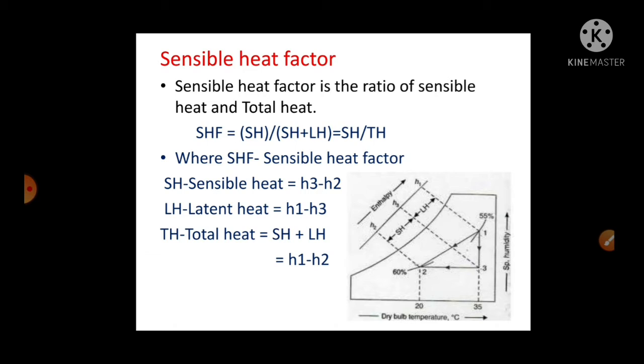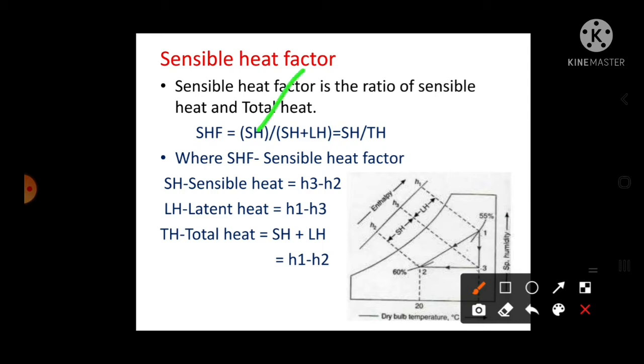Sensible heat factor is the ratio of sensible heat and total heat. So SHF is sensible heat divided by the total heat. So what is total heat? Total heat is nothing but the sensible heat and latent heat. Where SHF is sensible heat factor, SH is sensible heat, LH is latent heat, and TH is total heat. And total heat is the sum of sensible heat and latent heat.